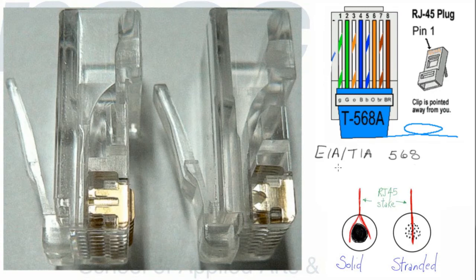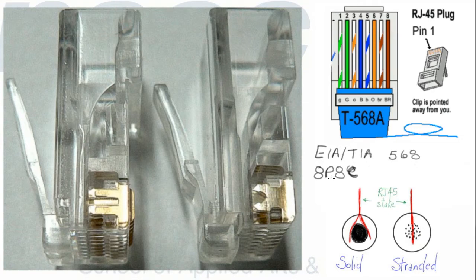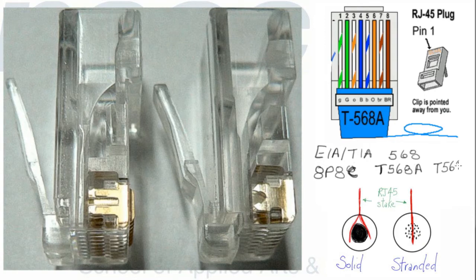They published two specifications for how you could put these colored pairs inside a connector. The connector is properly termed an 8P8C — 8 pins, 8 connectors. So it's an EIA-TIA 568 standard. The connector is actually an 8P8C, often termed an RJ45. The wiring standard adheres to one of two variations: it's either T568A or T568B.